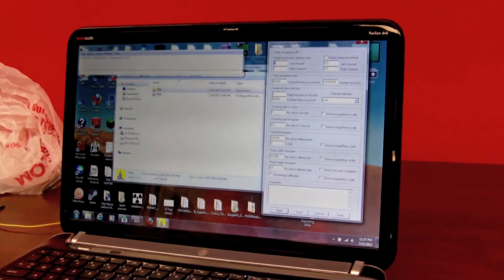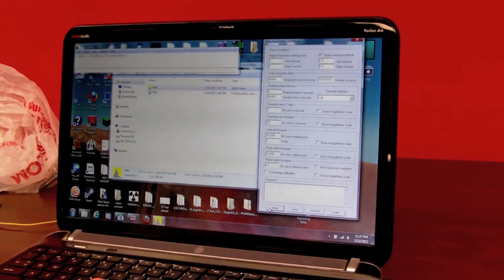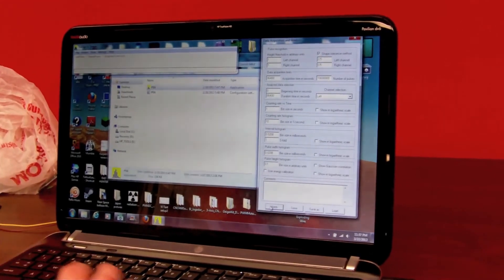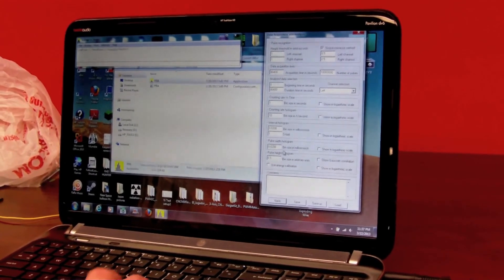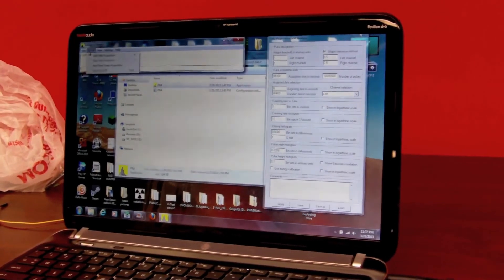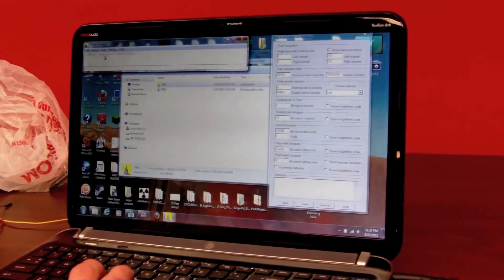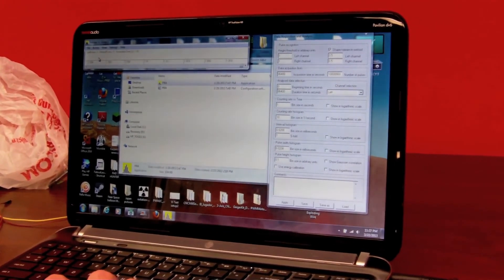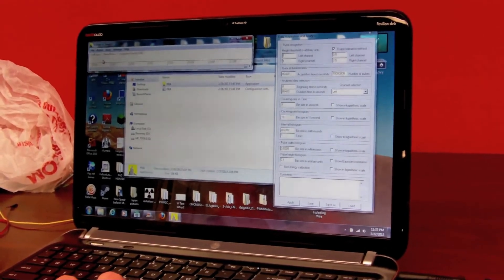Alright, so you're going to want to set in the data acquisition analysis, you're going to want to set the shape tolerance method. And what it's doing is looking for a specific pulse shape. It helps improve the data quality. And then we go to action, start data acquisition. And it's going to start counting pulses.